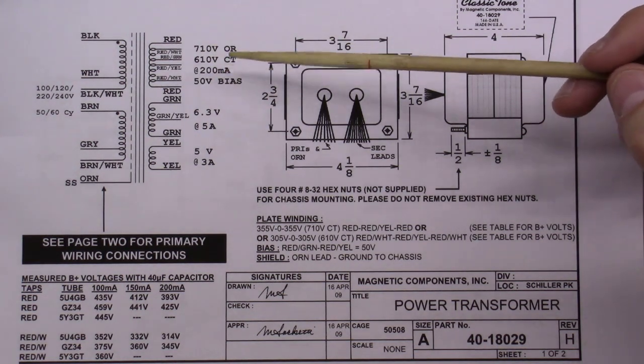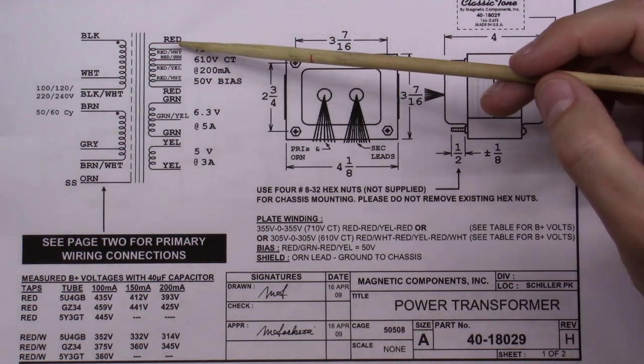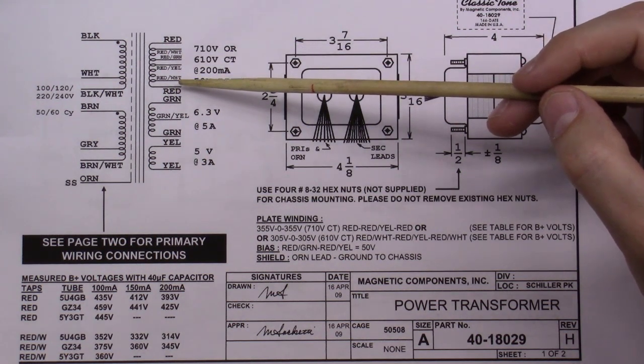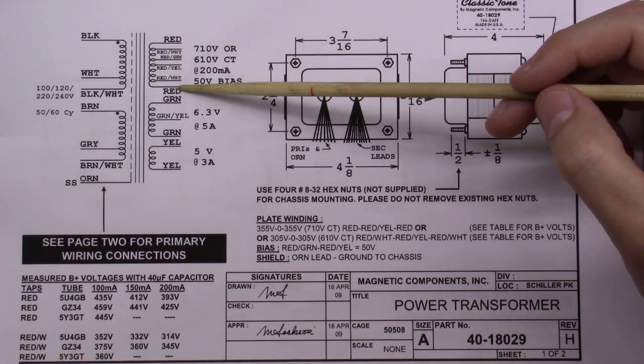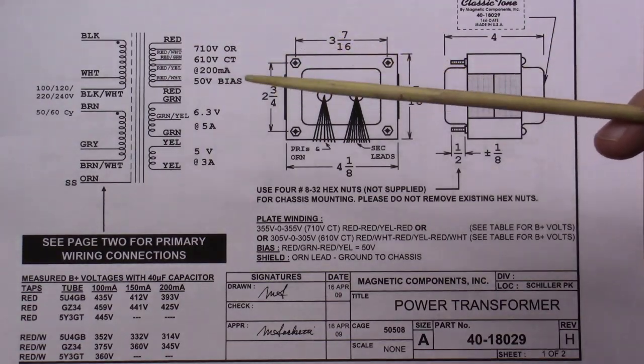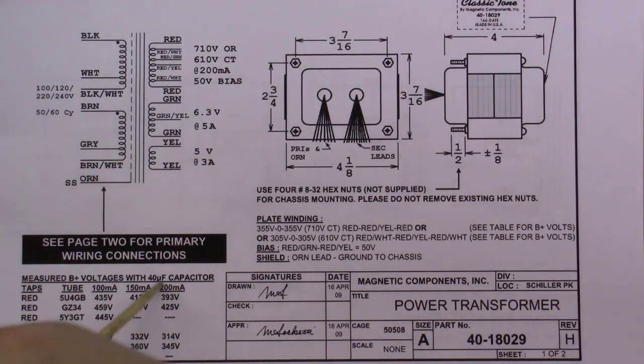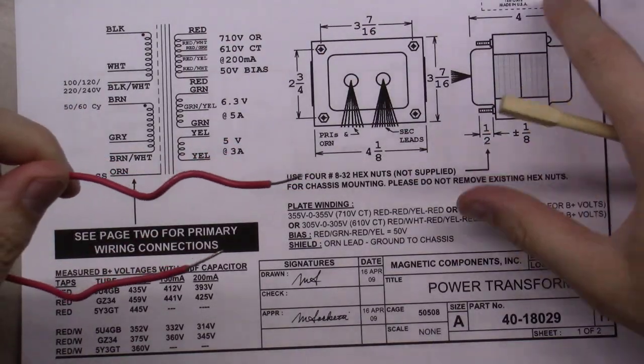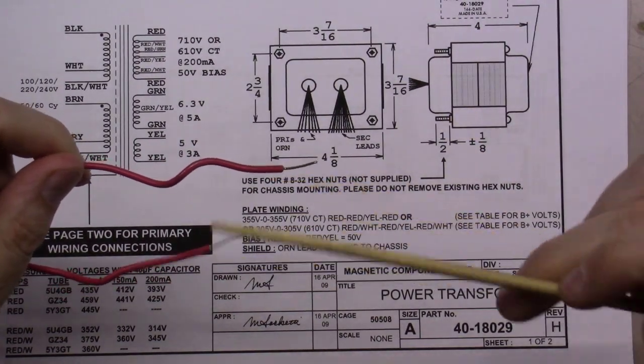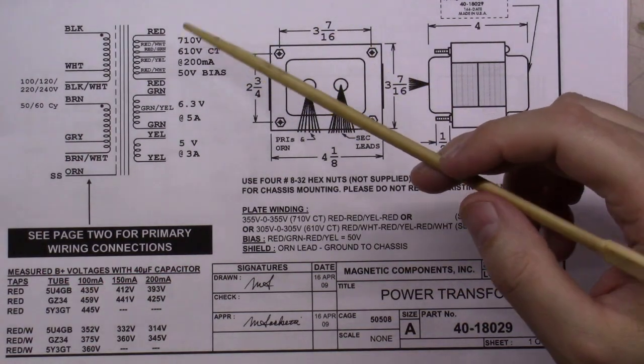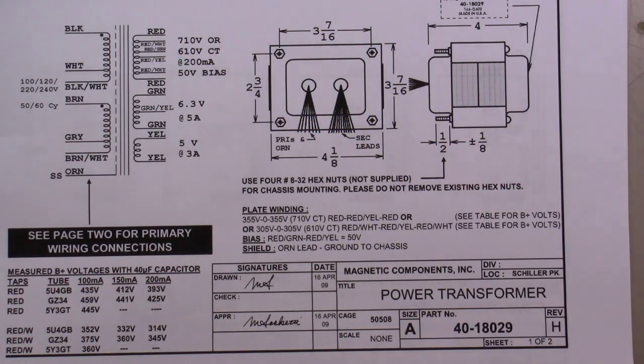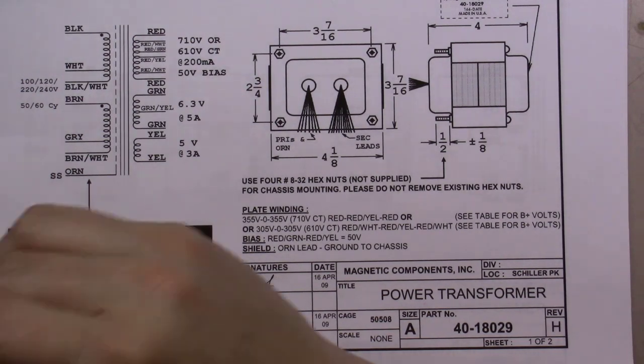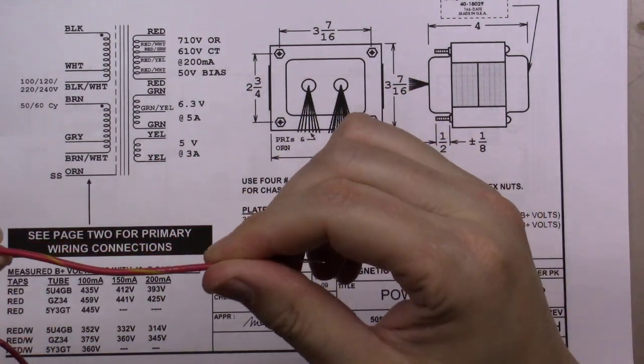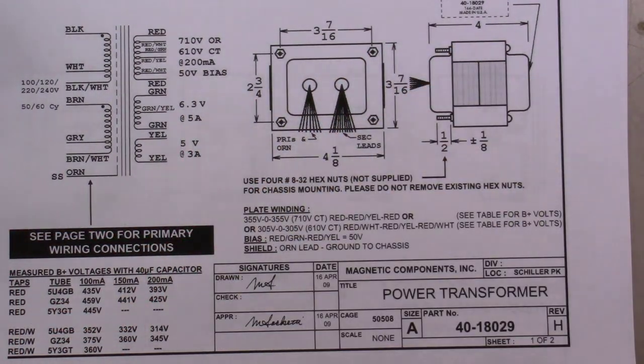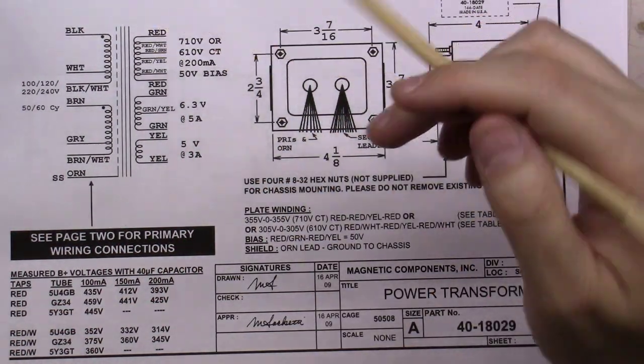But you don't want to use — notice this transformer has multiple windings here on the high voltage. The furthest out would be red and red. If you connected the two red wires together coming off this transformer, you'd have 710 volts across them. Notice the center tap here is known as red-yellow — you can see the yellow on this wire. So those are the three wires we're going to use for the high voltage on this thing.